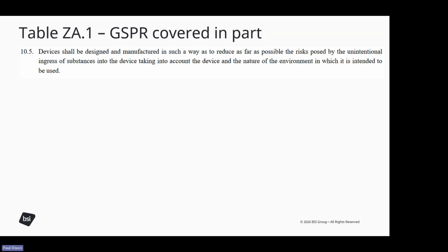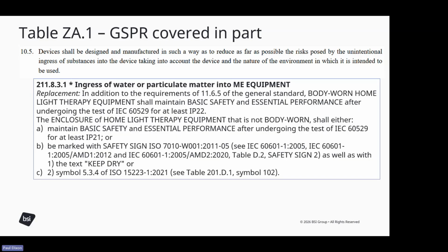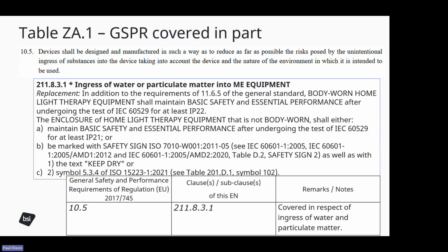Another example, unintentional ingress. So again, this is from IEC 60601-2-83, which is a TC62D standard for home light therapy equipment. This is a standard that's written in the 60601 style with the clause numbering beginning with 200. 211.8.3.1, ingress of water or particulate matter. This one is actually referencing clause 11.6.5 of the general standard, but it has some very specific requirements. So, for example, the IP rating being at least IP21, the use of safety signs and symbols. So this was accepted by the assessors. So it addresses clause 10.5 in respect of ingress of water and particulate matter.